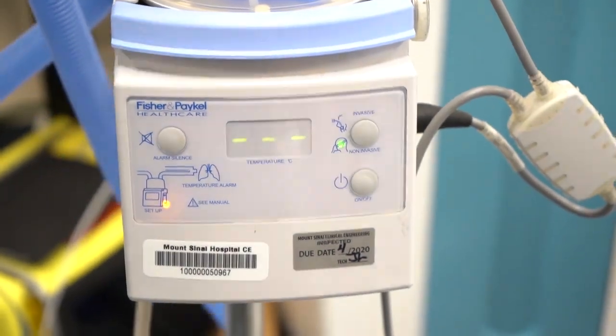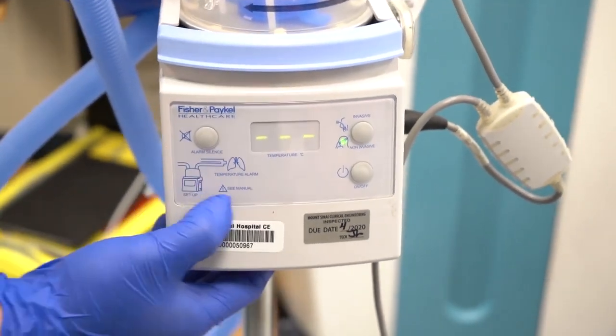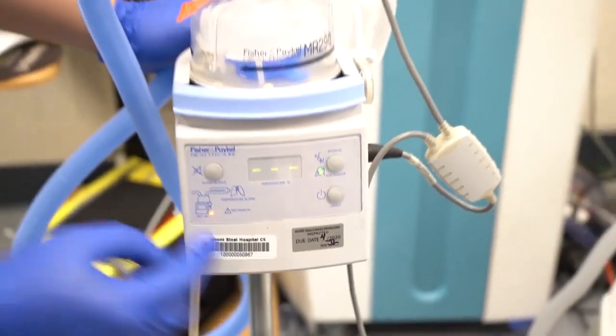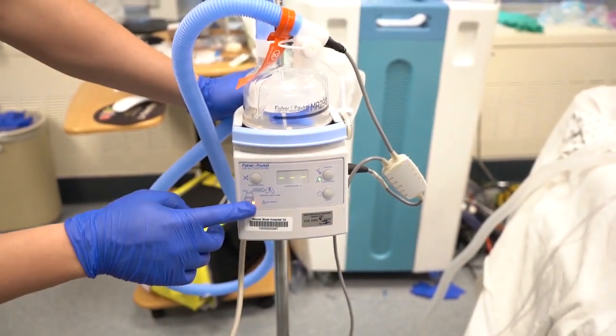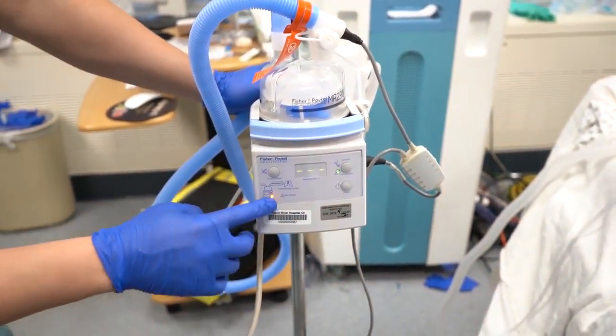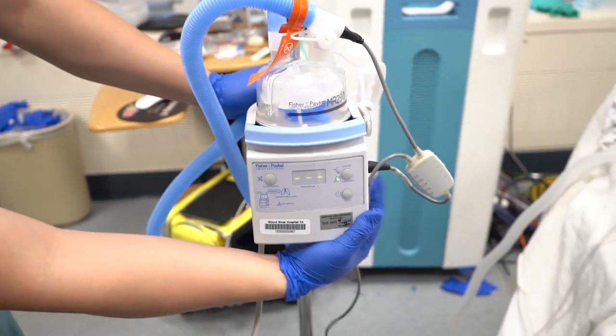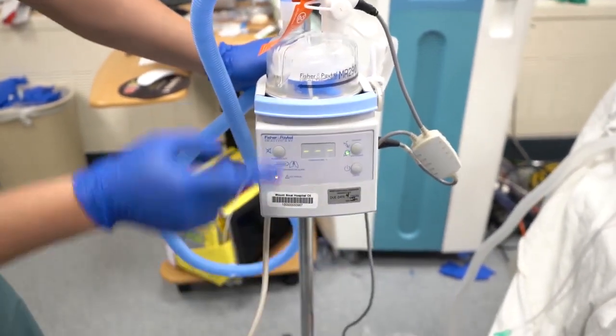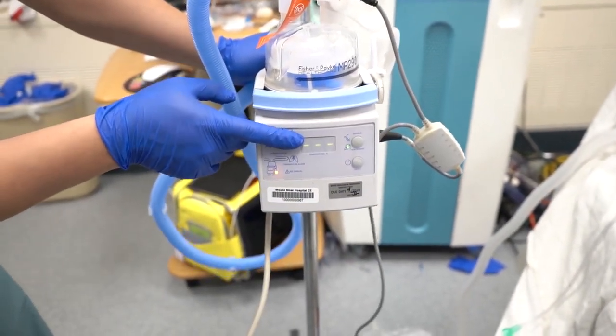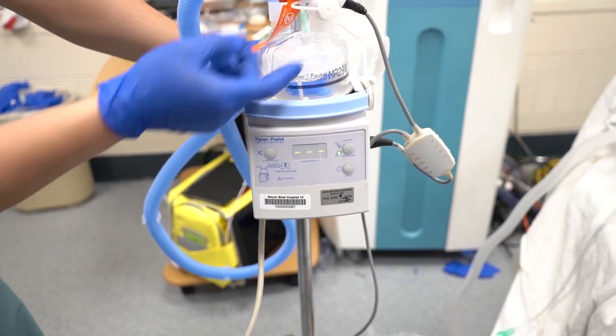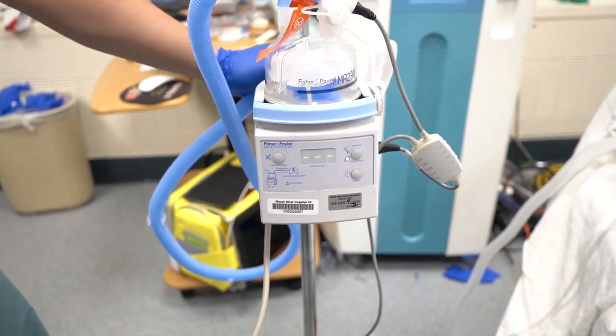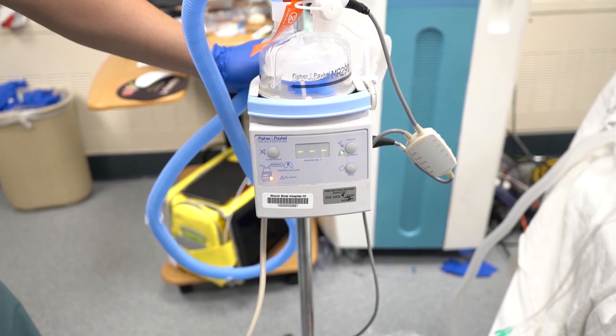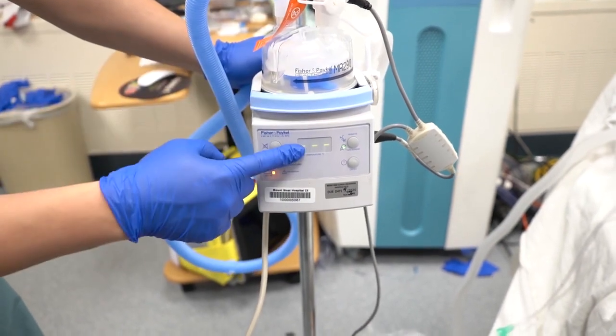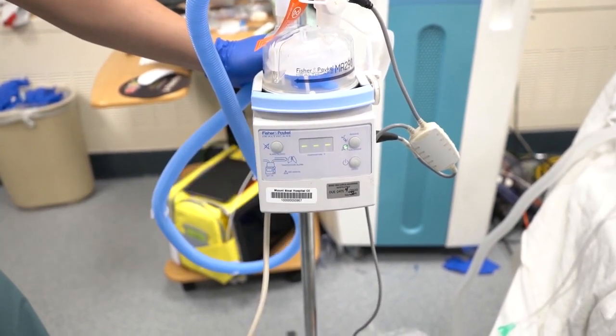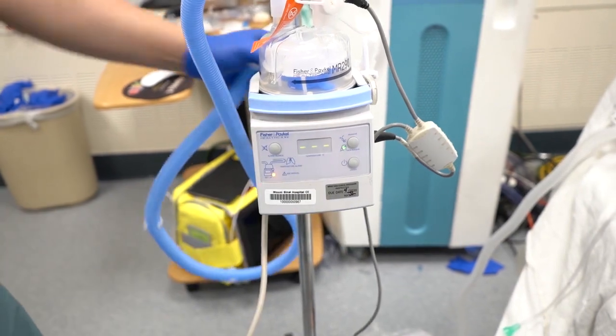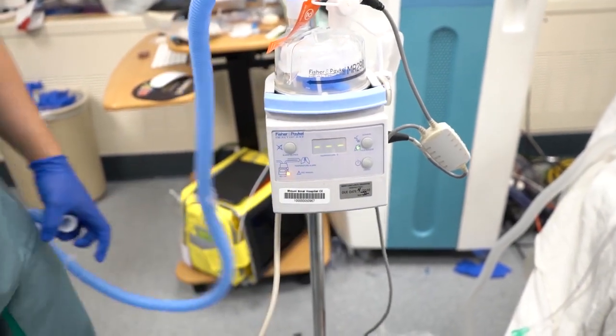For any troubleshooting involving the heater, right now since there's no water and no temperature probe, it's going to light up where the error is happening. Right now it's lit up where the temperature probe should be, and you're not going to see any readings on here because there's no water going through and no temperature probe, so there's no temperature being read. But if there was, then you would see the temperature displayed on this display instead of dotted lines.